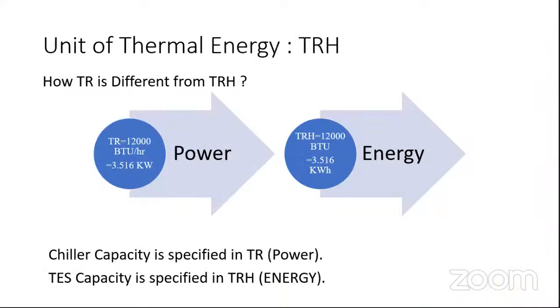What is the unit of thermal energy storage? So the unit of thermal energy is ton hours. One ton is 12,000 BTU per hour. So that is essentially a power. When we convert that to energy, it becomes ton hours. So when we multiply tons by hours, it becomes BTU, which can also be converted into kilowatt hours. So that's energy. So chiller capacity is specified as tons, and thermal energy storage capacity is specified in terms of ton hours.